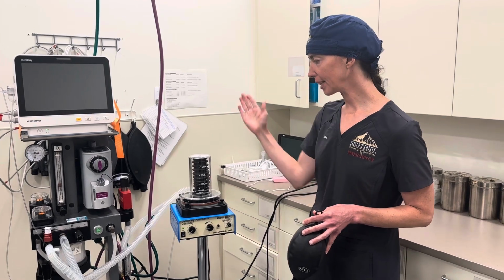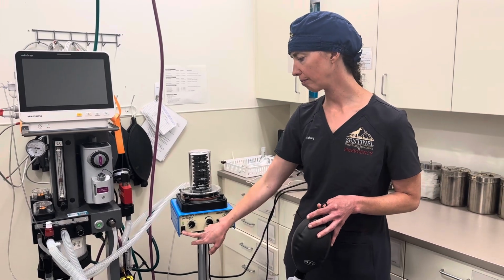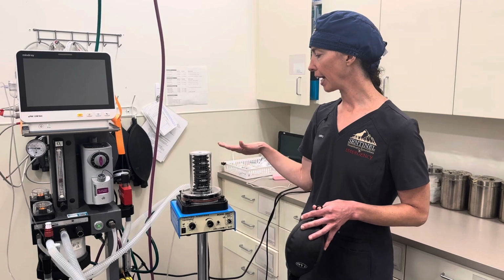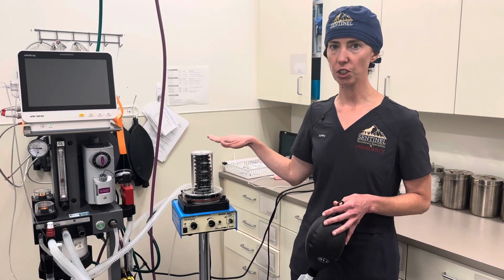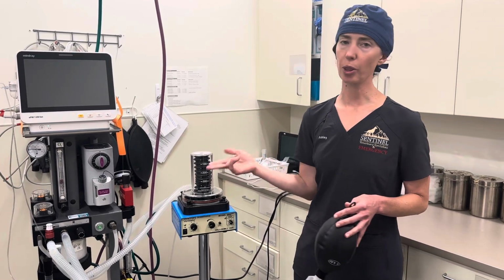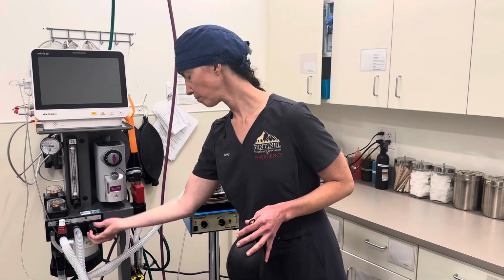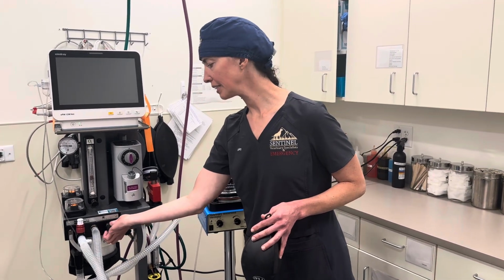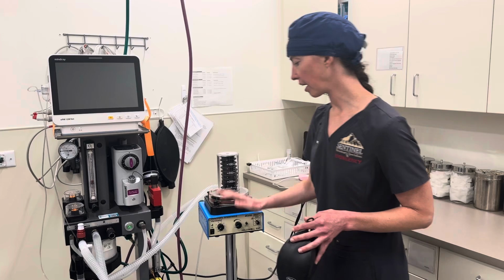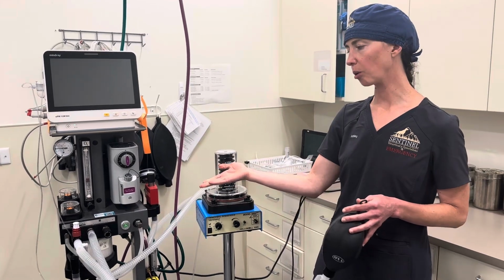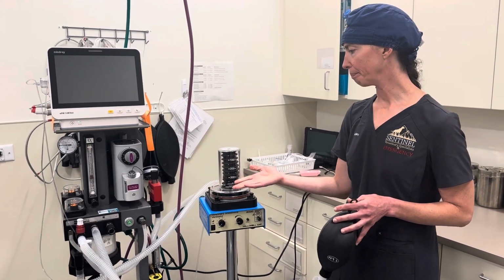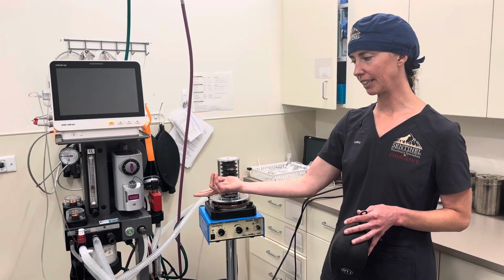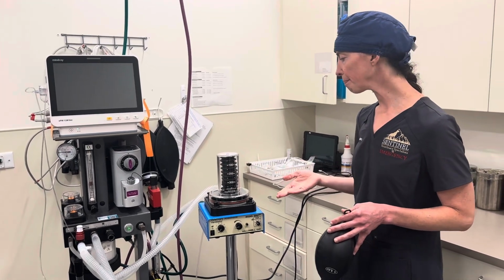So taking them off the ventilator, you can hit the off button, and then the next thing I would recommend you do once you hit the off button is to open the pop-off valve here. And if you get into that habit of, okay, every time I turn the ventilator off, I open my pop-off valve, it tends to prevent us accidentally leaving it closed when we switch them.